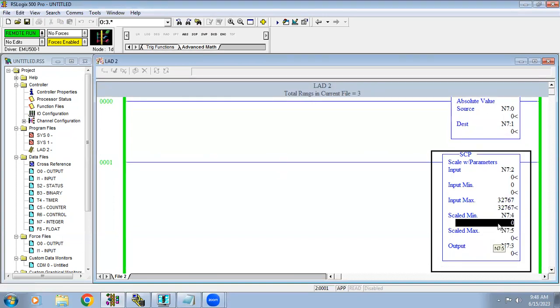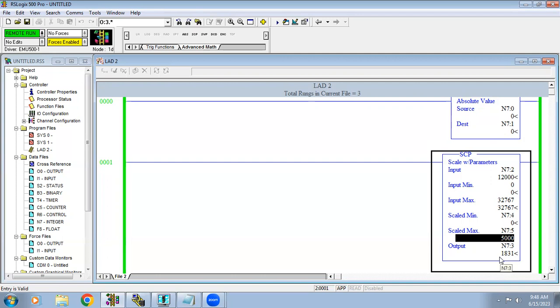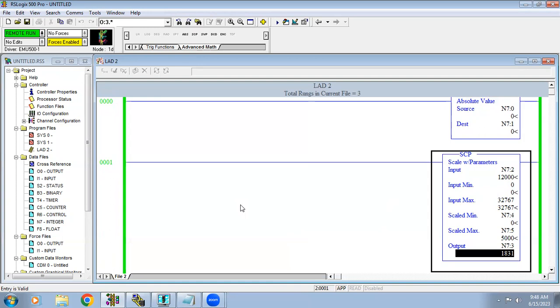If you want to change the range at runtime, instead of giving direct values in the scaler, give addresses. So at runtime we can adjust the range — for example 4 to 20. When I enter 12, it shows the corresponding scaled value. If you say 0 to 5000 liters, it shows in liters. This is the usage of the scaling function — in HMI we can display the exact value to the operator, since operators don't need to know PLC programming details.